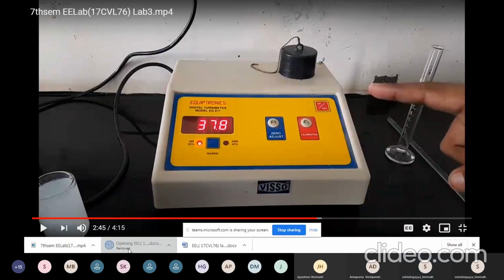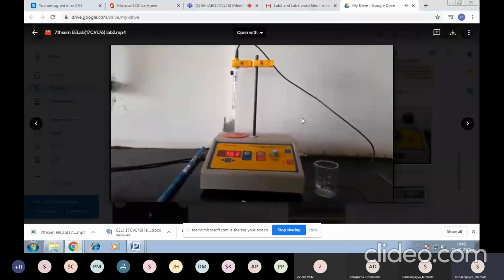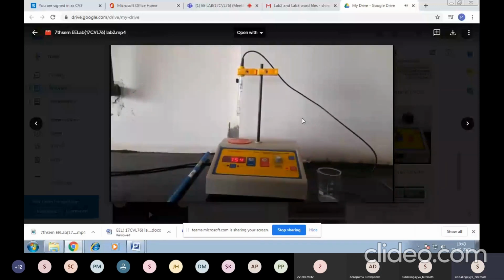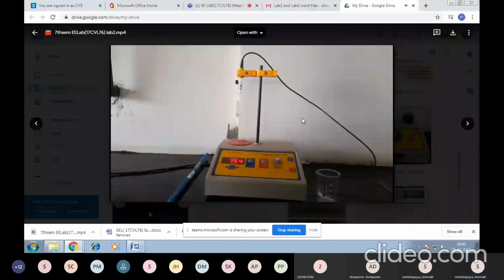Now, the bottom part is a bulb at the end of a glass tube containing a reference solution of fixed pH. A calomel or silver chloride, that is, silver/silver chloride reference electrode, is usually located around the glass electrode system for sample operation.